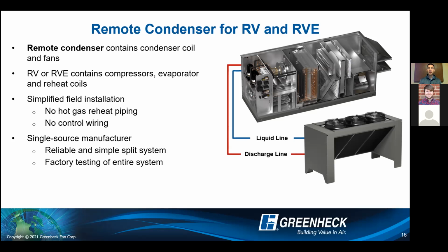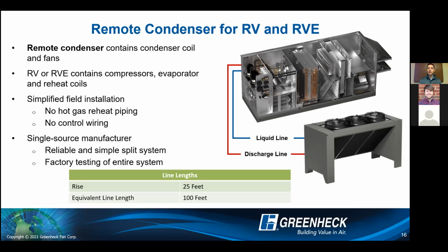We're going to pipe them, pump them full of refrigerant, fully test them at factory, and then obviously evacuate the system, plug them up, and send them both on their way. But this gives you the ability to know you're getting a reliable split system. We're controlling the compressor modulation. We're handling the reheat flush sequence, but you're still getting that split system design that would be required for that application. So some line lengths to be aware of with this remote condenser.